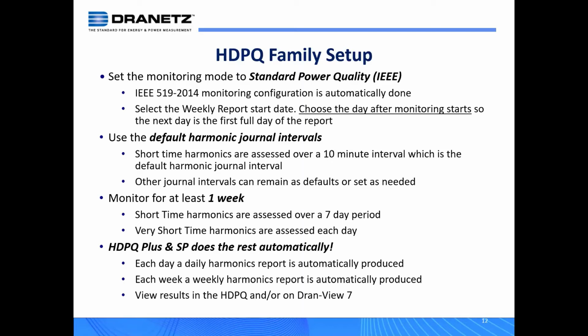And so we're going to give you a couple slides here on those setups, but I'm also going to go through an online demonstration on how to do that, followed by some data that's been recorded, and we'll show how that's reported in DranView. So the first thing here is to set the monitoring mode to standard power quality IEEE, and that keys the instrument to do things the IEEE way. And there's another one for IEC, which does not enable this reporting. So if you're in Europe or other parts of the world that follow the IEC monitoring, we would suggest that, and that would be standard power quality monitoring for IEC. So we're going to choose IEEE here.